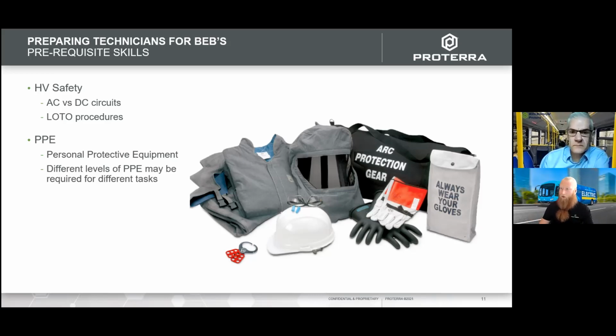We can go a step further with shock hazard PPE. Once you've confirmed voltage is absent and verified there's no presence of voltage in any of these circuits, you can, in most circumstances, step down the level of PPE. So let's say you're wearing EH-rated safety shoes, high voltage rubber gloves with overlays, and safety glasses — that's what's required for shock hazard. Once I've confirmed there's no voltage present, I can take the rubber gloves off and do the needed work, until the point where I'm testing again for voltage, where I may have to put on a different level of PPE. Those are the varying levels we're discussing here.